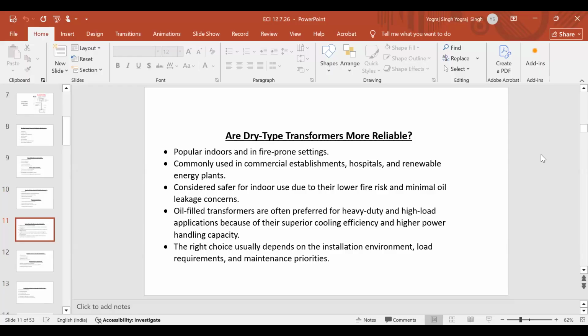So the question is, are dry type transformers more reliable? They will not see frequent faults, as they don't require filtration of oil and other things. But at the same time they are costly and they will require more ventilation system in the basements, which is generally not available.